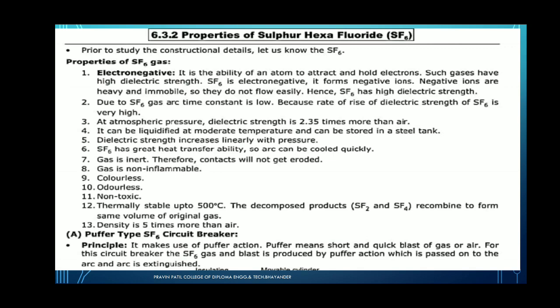SF6 is colorless, odorless, non-toxic, and thermally stable up to 500 degrees Celsius. That means this gas is stable at a temperature of 500 degrees Celsius. The decomposition products are SF2 and SF4, then they recombine to form SF6. The recombined form of the same volume is the original gas. Density is 5 times more than air. These are the properties of SF6 gas, sulfur hexafluoride gas.